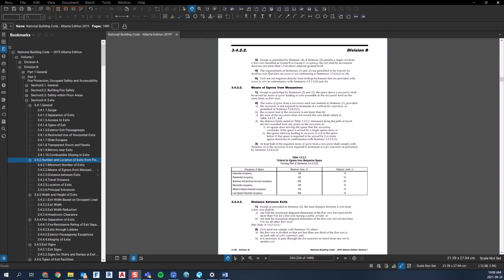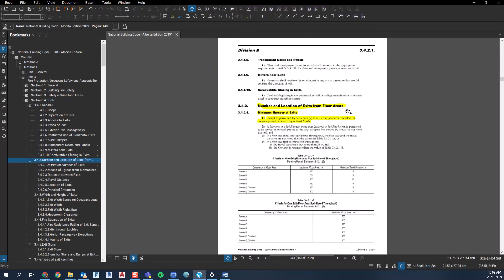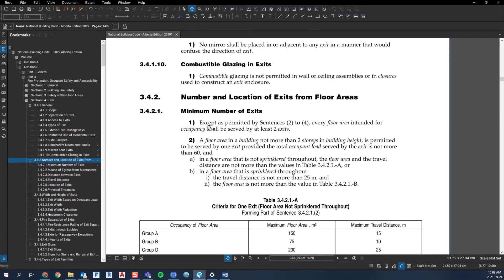Let's look at the National Building Code Alberta Edition, Section 3.4. We're in Division B, Part 3, and we're going to look at Section 3.4, which is about exits. We're going to focus specifically on Section 3.4.2 — the number and location of exits from floor areas. Right off the bat, it says under minimum number of exits: every floor area intended for occupancy shall be served by at least two exits.